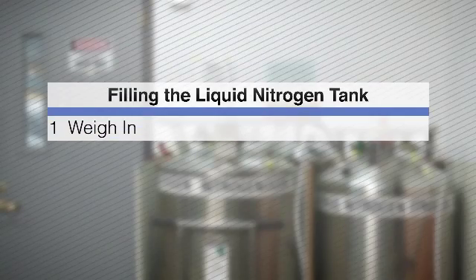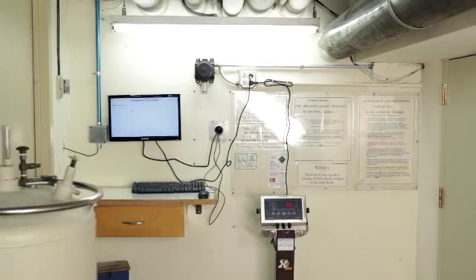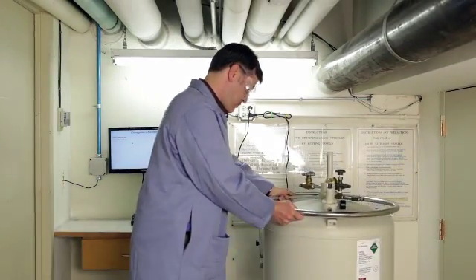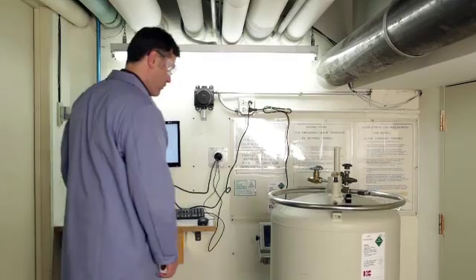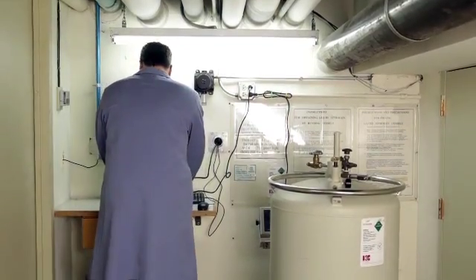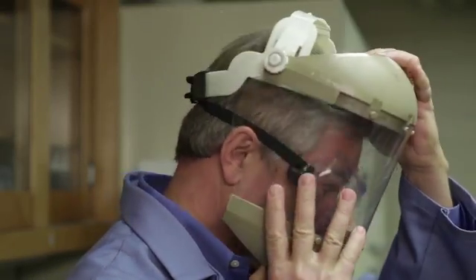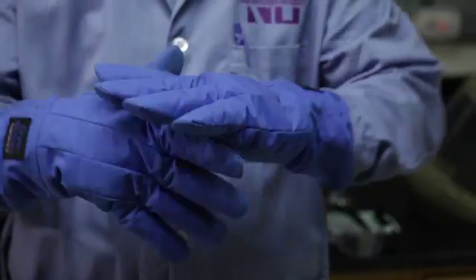When refilling your tank at a fill station, follow all posted procedures. Step 1: Weigh in. Begin by weighing your empty tank on the scale and record the empty weight, your name, the current date, and the account to which the service should be billed. Before attaching your tank to a fill station, don the proper personal protective equipment. Step 2: Attach the tank. Place the liquid nitrogen tank directly in front of one of the fill stations.